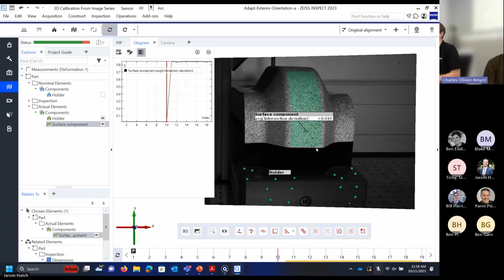All right, so over here I inspect my surface component, looking at the average intersection deviation across the whole surface. You can see over time we have really good intersection, very, very small, 0.019 pixels, well within our limits. Then we have some abrupt change. Now our intersection deviation is 0.8, well above our 0.3, the maximum we'd like to see. And it stays there over time.